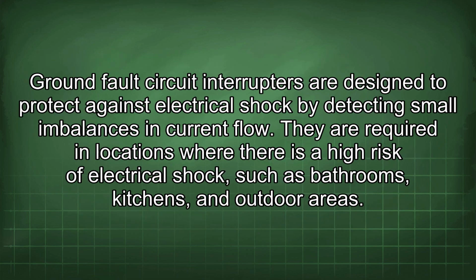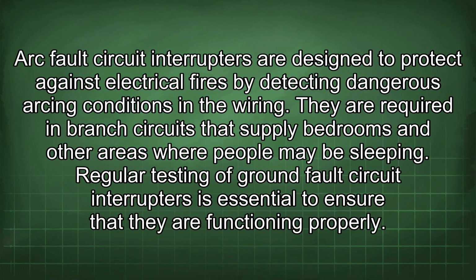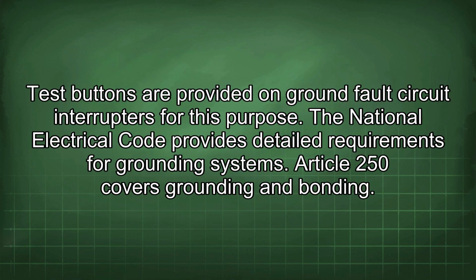Ground fault circuit interrupters are designed to protect against electrical shock by detecting small imbalances in current flow. They are required in locations where there is a high risk of electrical shock, such as bathrooms, kitchens, and outdoor areas. Arc fault circuit interrupters are designed to protect against electrical fires by detecting dangerous arcing conditions in the wiring. They are required in branch circuits that supply bedrooms and other areas where people may be sleeping. Regular testing of ground fault circuit interrupters is essential to ensure that they are functioning properly. Test buttons are provided on ground fault circuit interrupters for this purpose.